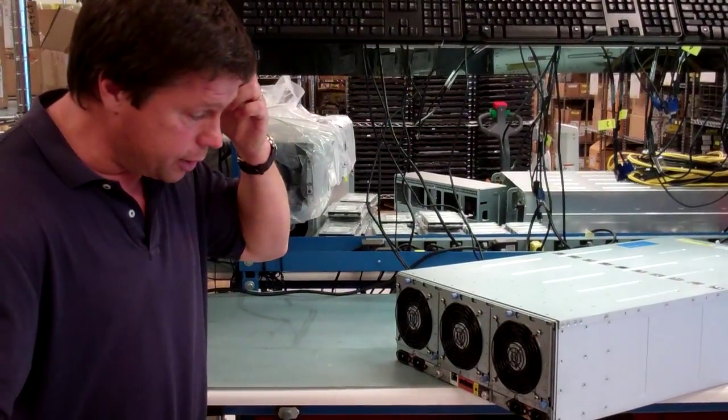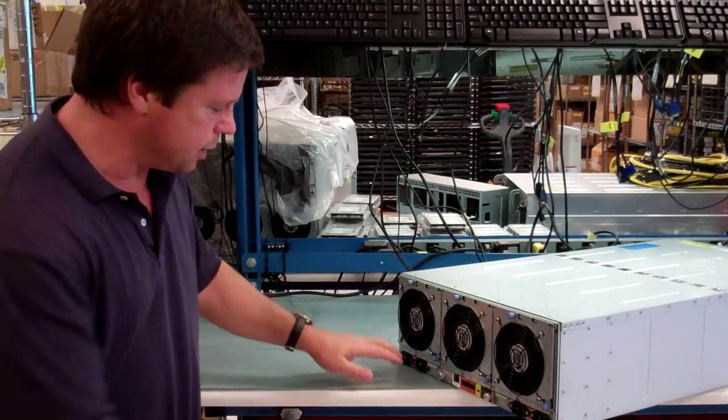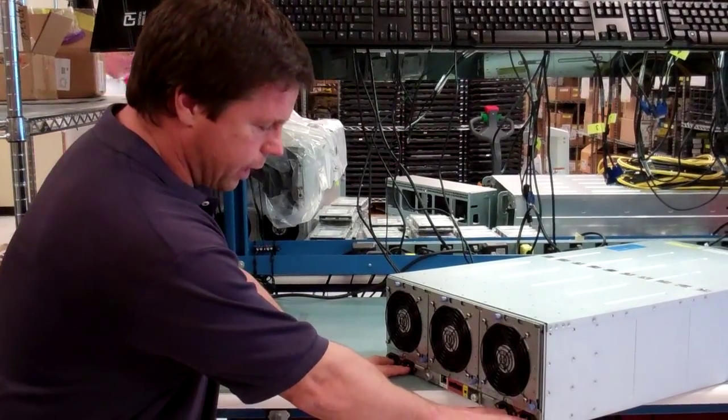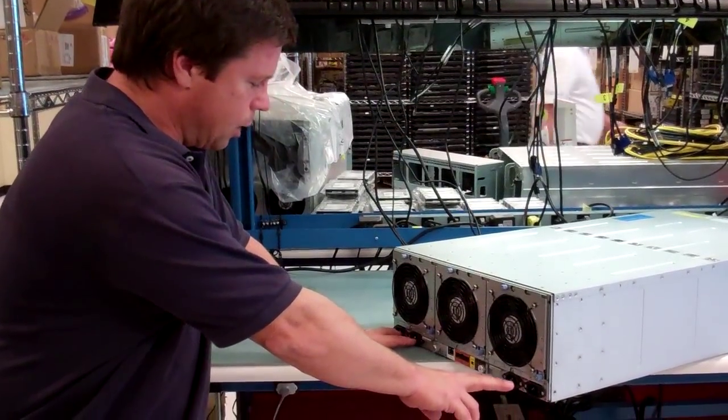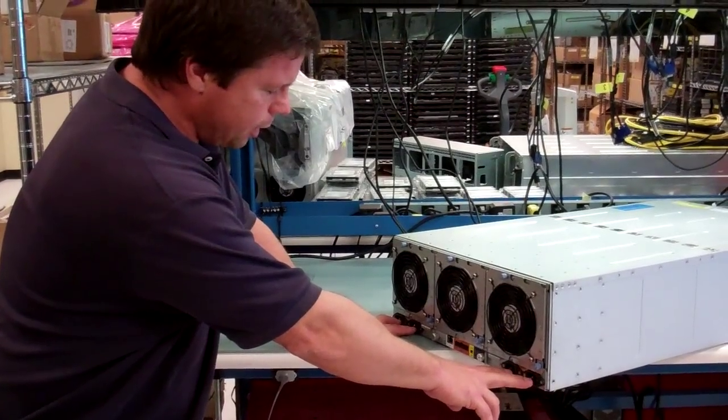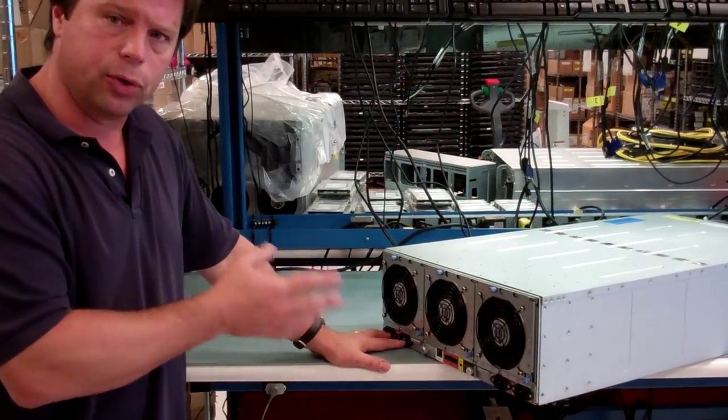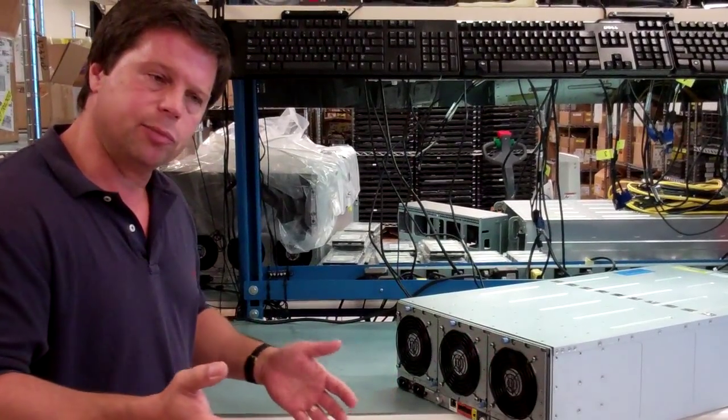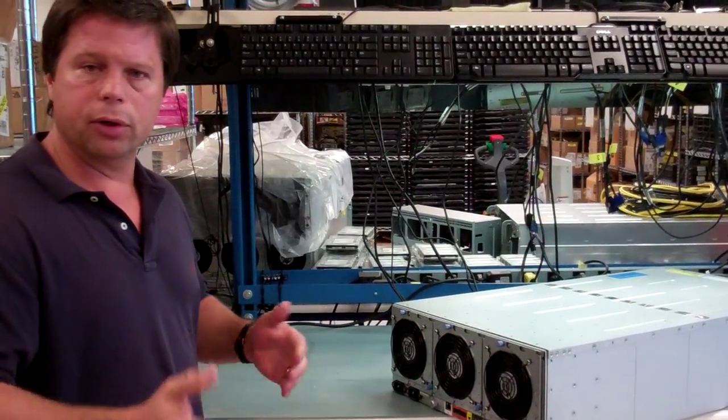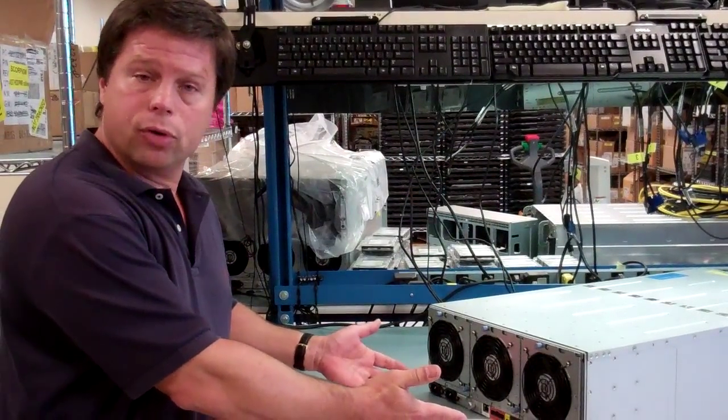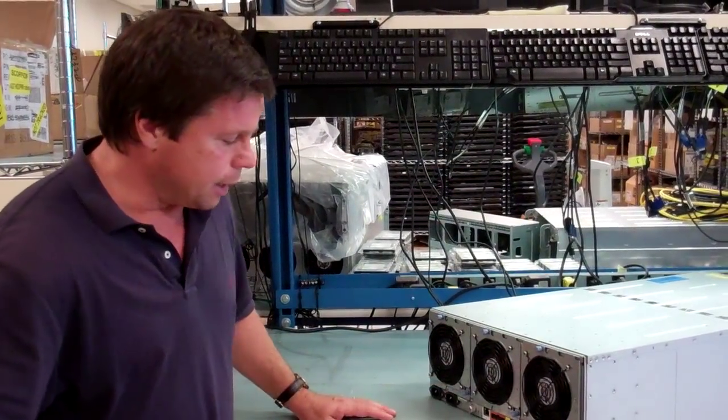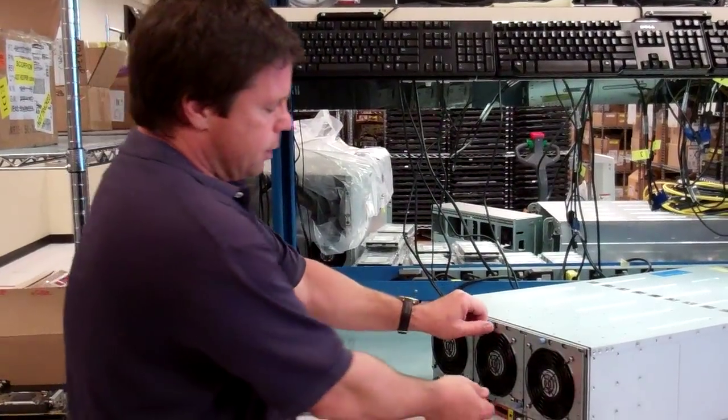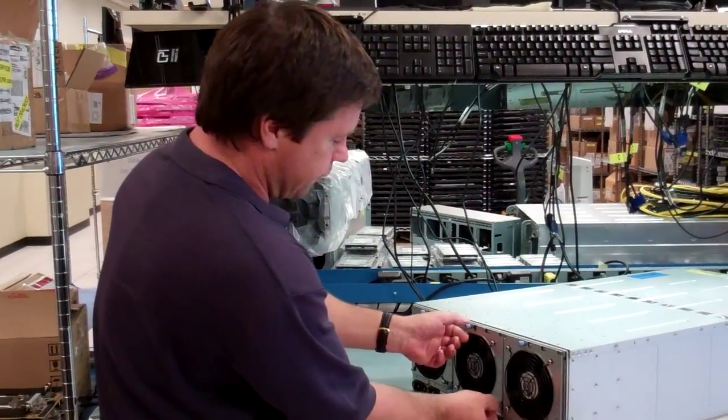A couple of things that are here in the back that might be serviced. Notice that we have the four AC plugs that go in. This chassis can support running off of grid A and grid B. So if a customer wants to have a failover power grid scenario, that can be supported directly with the four AC plugs that go in the back end.